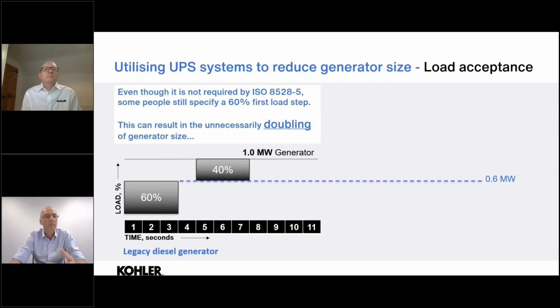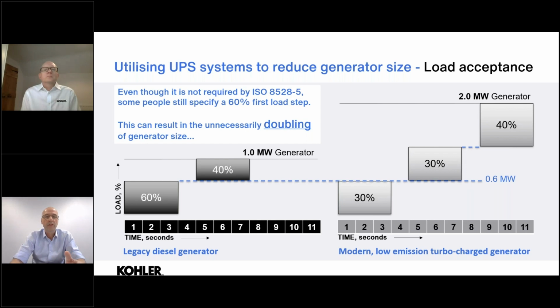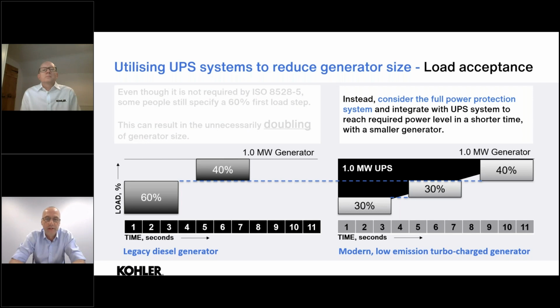So, you know, we still get people requiring or asking for the 50 to 60% load step as the initial step. Okay, and this is, you know, legacy, and yes, everybody wants to get the load on as quickly as possible, as fast as possible in the least amount of steps. Now, what we should do is sort of look at the ISO standard. If you were to ask for that 50-60% load step at the beginning, with a modern engine that wouldn't be able to accept that, you'd have to increase the size of the generator to match. We've got an example here of a 1 megawatt load. So 60% of that is, you know, 600 kilowatts. So we're potentially having to double the size of the generator to have that 60%, that 600 kilowatt load step initially. What we should be doing is looking at the whole power protection system as a whole.